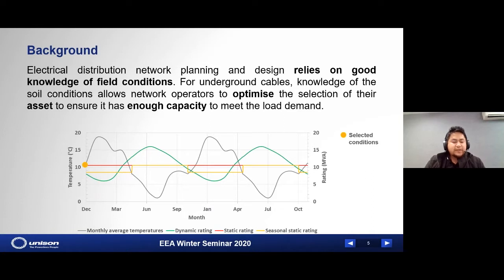So we can perform different things to do rating studies. We can use a static value, labeled in red. We can use seasonal rating, having summer and winter values. We can also perform real-time monitoring on the field to collect soil temperature, for example, so we can identify what capacity we can apply to the cables based on known field conditions.